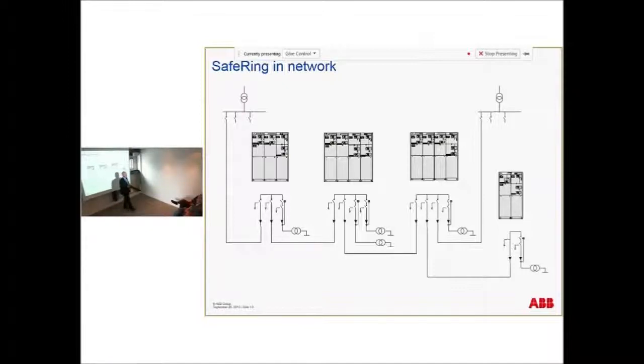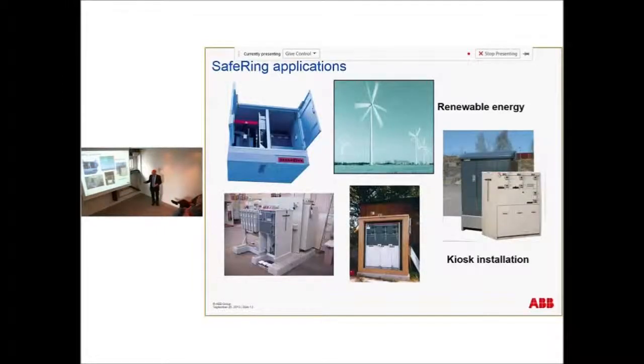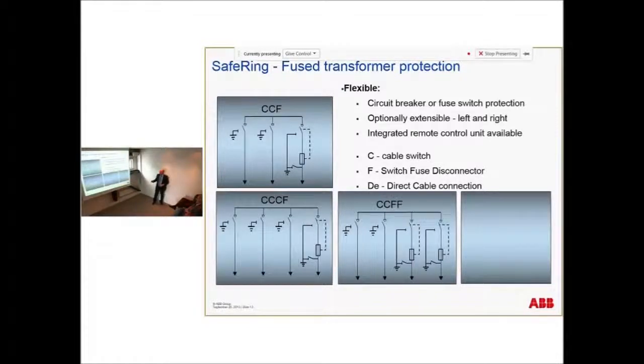This switch is a load break switch. And for the Safe Ring applications, you can see we have 1, 2, 3, 4 units which are standardized from the factory. And here you see some applications where they are used inside a small enclosure, or in a windmill, and this one is a concrete station in Germany. This switch is a 3-position load break switch, where it is connected, disconnected, earthed. 1, 2, 3. That's what we call a 3-position load break switch. And in the case of a fuse, you have the same switch, connected, disconnected, earthed. And for personal safety, when you earth it, both sides of the fuse are earthed.